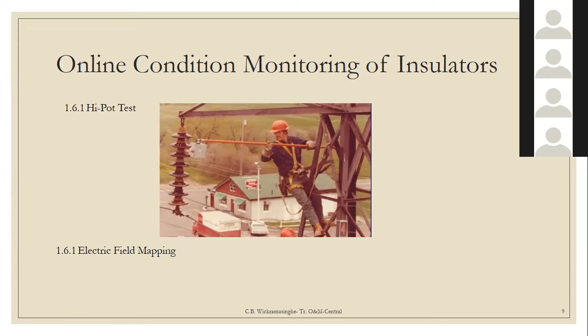So what I did was, I selected my sample of porcelain insulators: 10 brand new insulators, another 10 used insulators which were dismantled from the Badulla Mondraga transmission line, and another 10 porcelain insulators which were about to be disposed of at the transmission line maintenance unit. And also the glass insulators, the same way. This is my sample, porcelain and glass insulators. Then I took them to the Peradeniya HV laboratory in order to measure the flashover voltage and the leakage current.